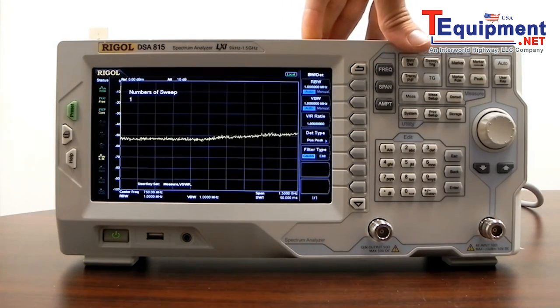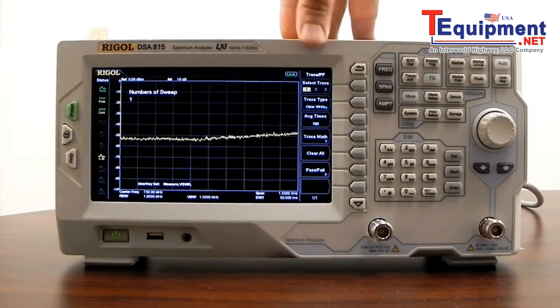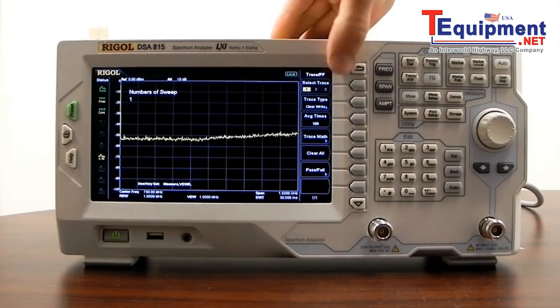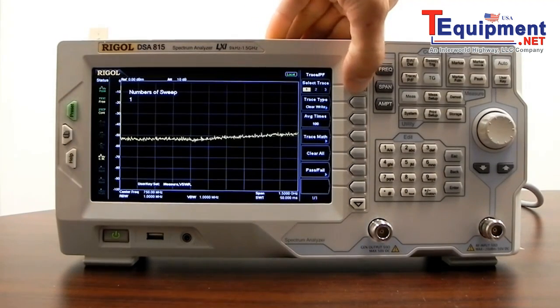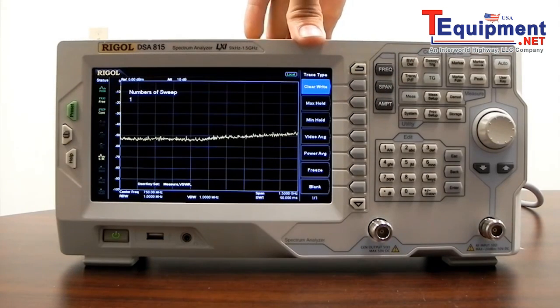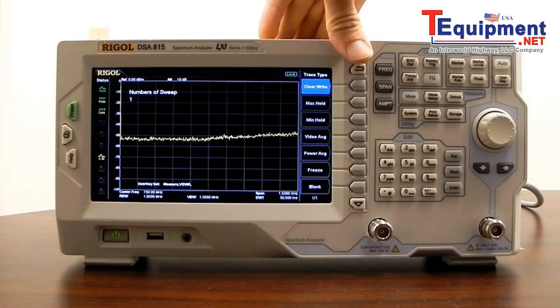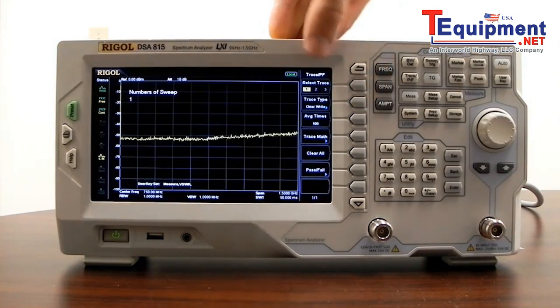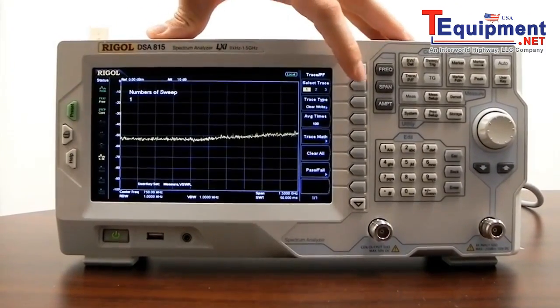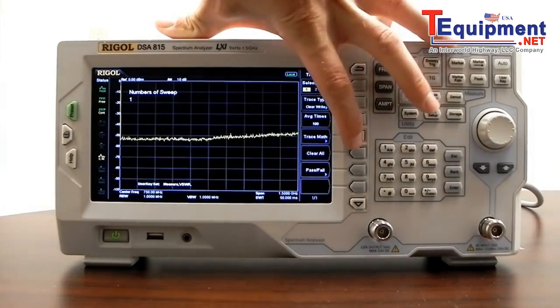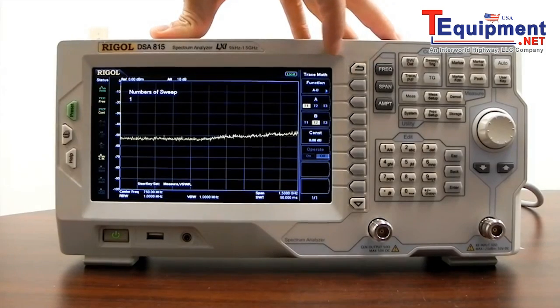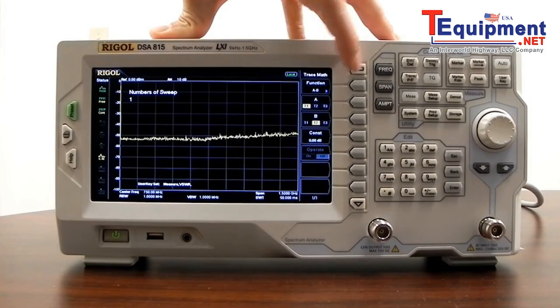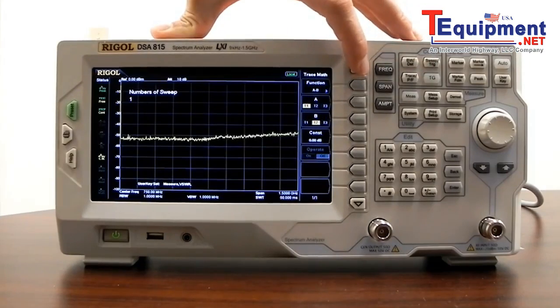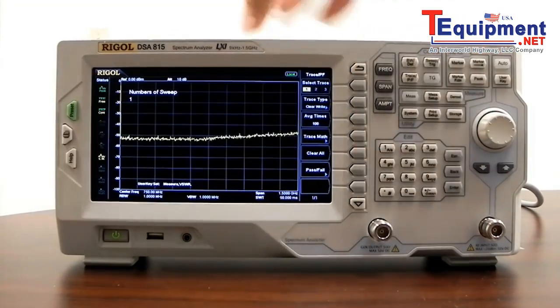Then let's move on to our trace. We have 3 traces that are selectable. In this case, we're doing trace 1. You can select trace 2 or trace 3. Then we have trace type. So we can do max hold, min hold, video average, power average, freeze, and you can also have a blank screen. The number of averages per trace is user selectable. We can also do trace mathematics if you want to add one trace to another trace, or perform basic math on those. You can do that and multiply by constants. We have clear all, which is going to clear the screen.